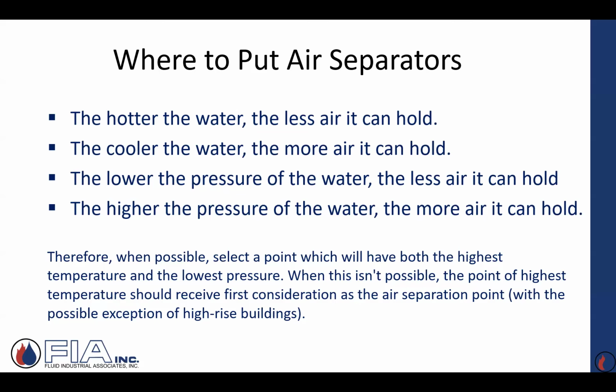And then when it's kind of not possible, ideally, highest temperature is going to have the most influence on releasing air out of solution. So again, that's why typically we're going to find air separators at the outlet of a heat exchanger, the outlet of a boiler or boilers. That's where I want. Now, when we get into pump location and how pump pressure differential can influence system pressure, if I'm on a suction of that pump, I haven't seen the pump's pressure, I'm at a lower pressure than what the system's going to see when that pump's adding its pressure differential. So at the hottest point, ideally at the lowest pressure if possible.